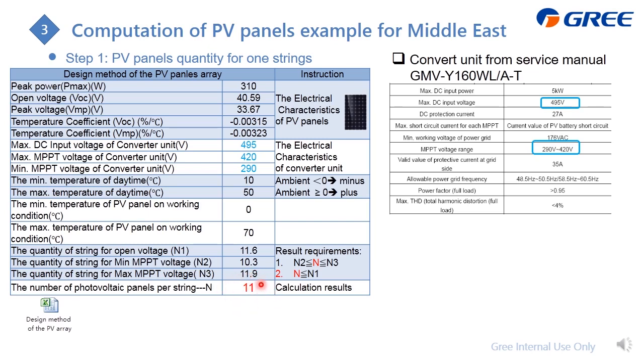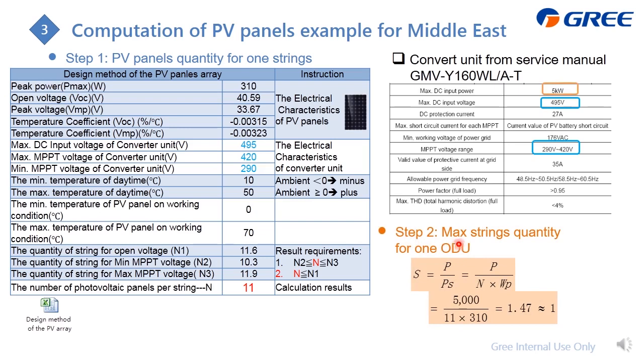For this case, one string has 11 panels. The next question is how many strings for this outdoor unit. Following the formula, S equals P over this—P is the max DC input, which is 5 kilowatts, N is the quantity (11), and WP is the max power output of one PV panel. The answer works out to only one string for this outdoor unit.